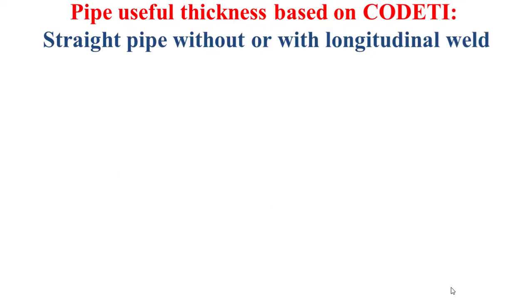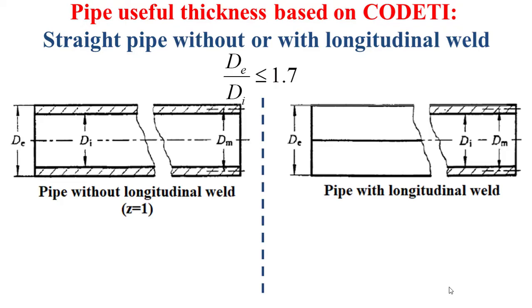Now, let's explain how to determine the useful thickness of the pipe based on CODETI, for the case of straight pipe without or with longitudinal weld. This case is considered when the external diameter of the pipe divided by the internal diameter does not exceed 1.7.